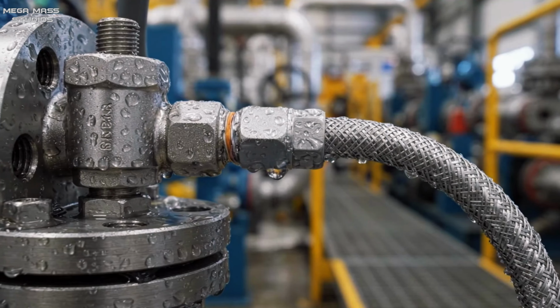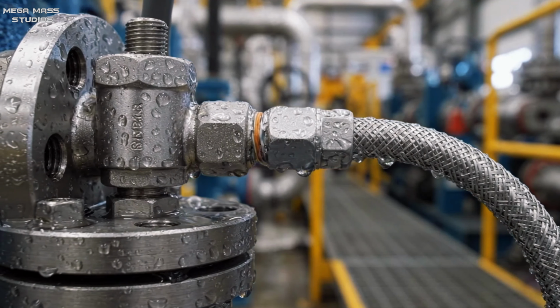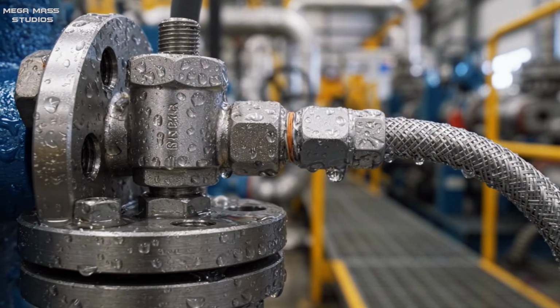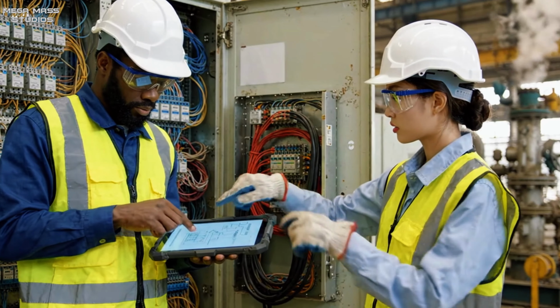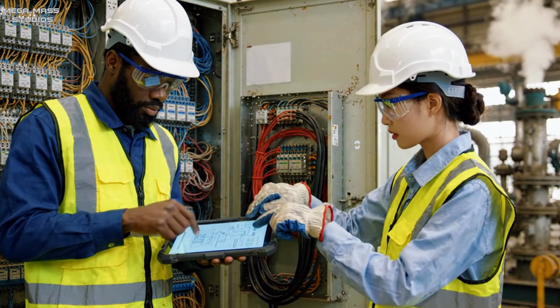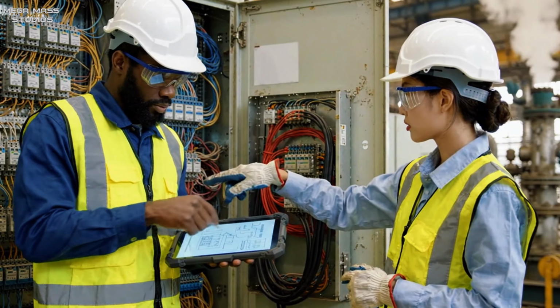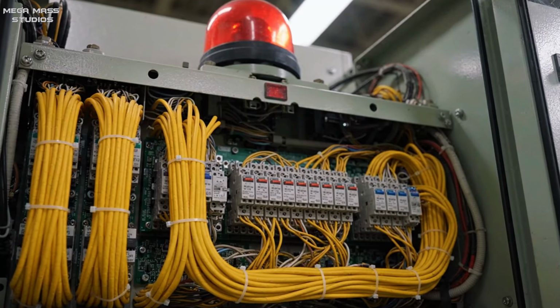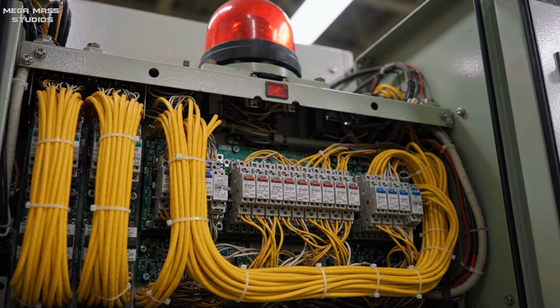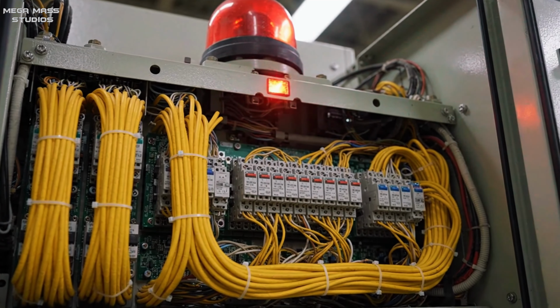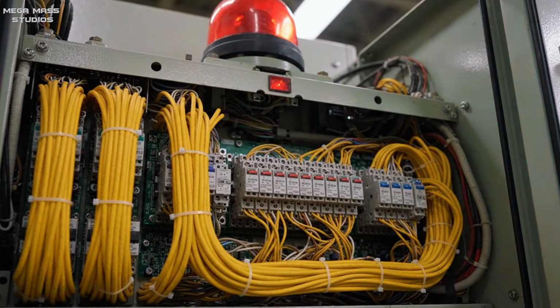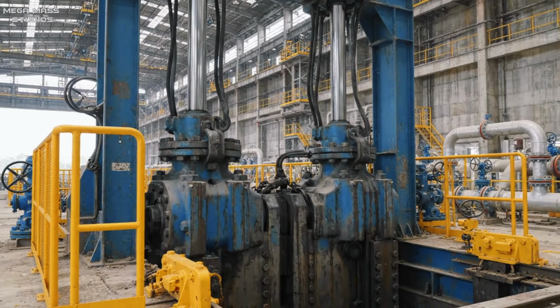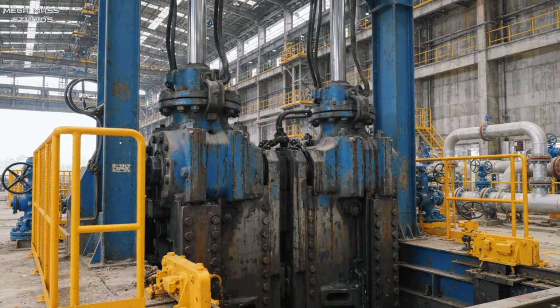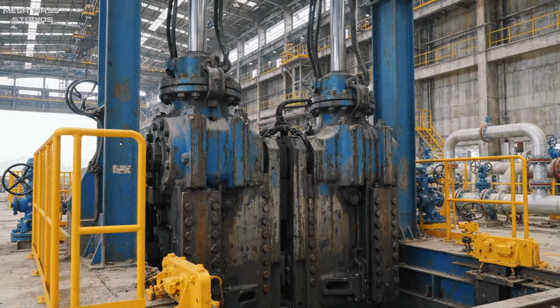The transition from velocity head to pressure head is monitored by dual redundant piezoresistive pressure sensors. These solid-state sensors transmit raw voltage data to the main PLC cabinet via shielded Ethernet lines. If the discharge pressure drops below safety thresholds, the control system initiates a sequence of emergency shutoffs. These emergency closures are managed by massive, fast-acting hydraulic piston-driven gate valves at the discharge outlet.